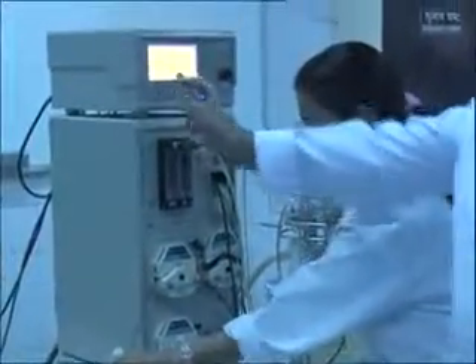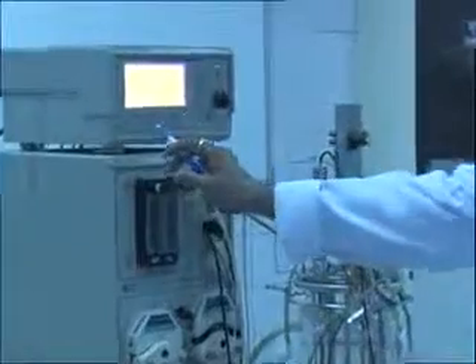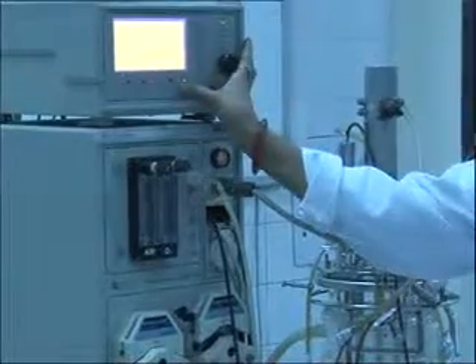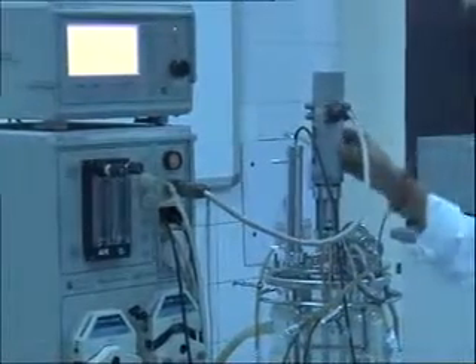So here we have all the measured parameters of the pH, temperature, dissolved oxygen, and we can see that everything is working all right. Now we stop the agitator, take the reactor to the autoclave, autoclave it at 121 degrees centigrade at 15 psi for 20 minutes, and then bring it back.